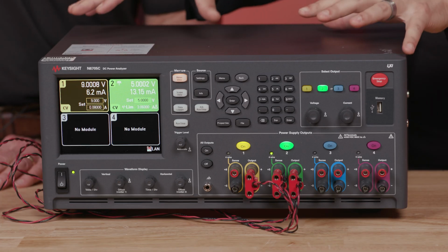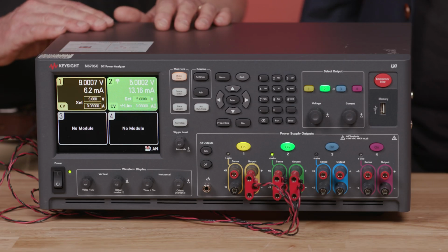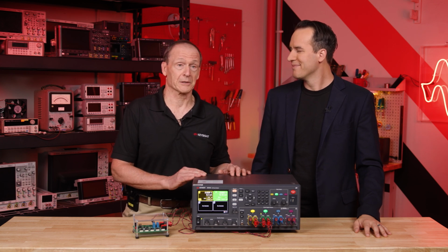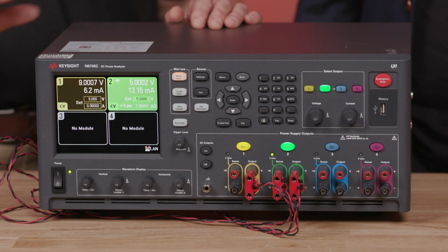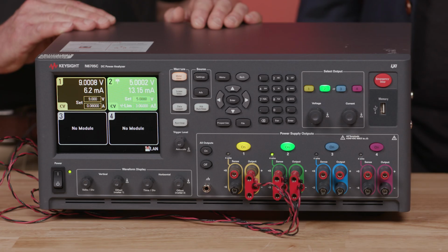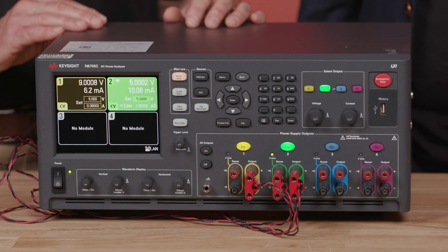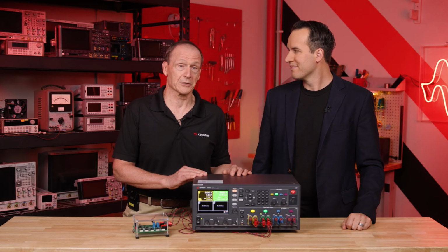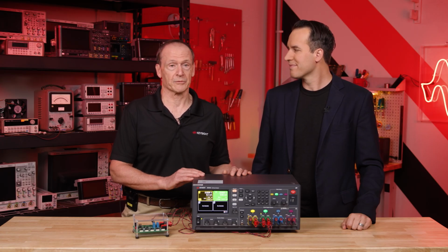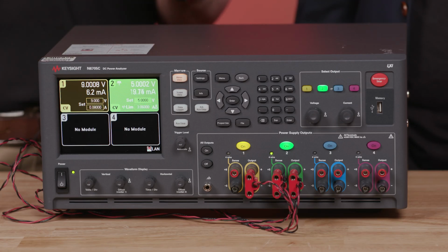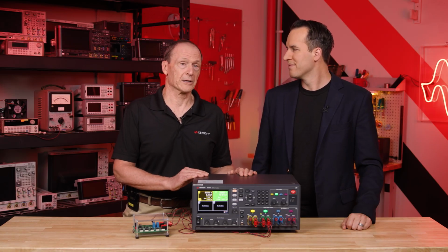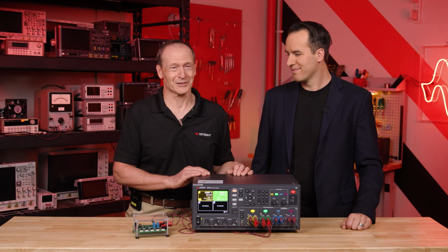Talk me through what you've brought in today. Okay, so today I brought the N6705C DC Power Analyzer, and it's got a variety of different modules and features available for it. In this particular case, I'm using the SMU modules, source measure units, because they have some very nice features I'll get into in a minute about seamless measurement ranging. But this product is very popular. It has a scope feature, a data log feature. You can data log things for long time periods. And it's very good at looking at IoT devices, as you had just mentioned.